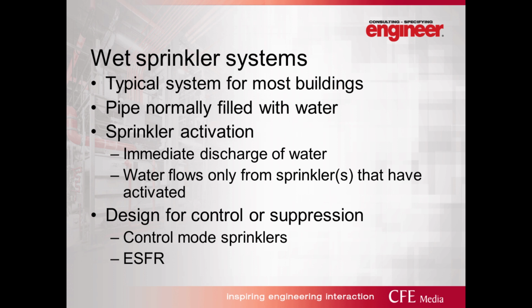My wife knows I get bent out of shape a lot when we're watching a movie and something will happen and a sprinkler will activate and all of a sudden the entire room dumps water. That is not a typical sprinkler system. Sprinkler systems discharge based off of an actual single sprinkler activating at a time. So it's not a complete dump. You don't activate a sprinkler and the whole room gets flooded with water. That's a Hollywood thing, and I tend to get a little bent out of shape when I'm watching that in a movie and see it happen.